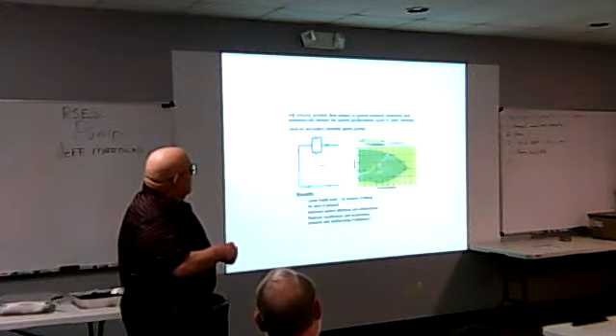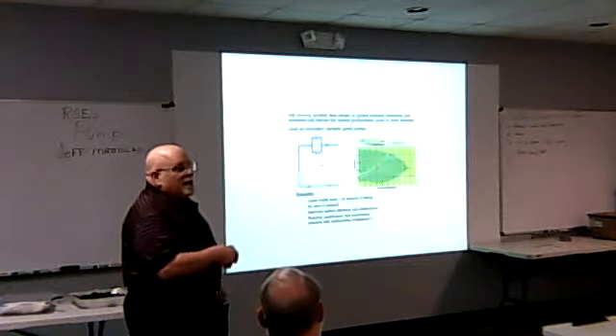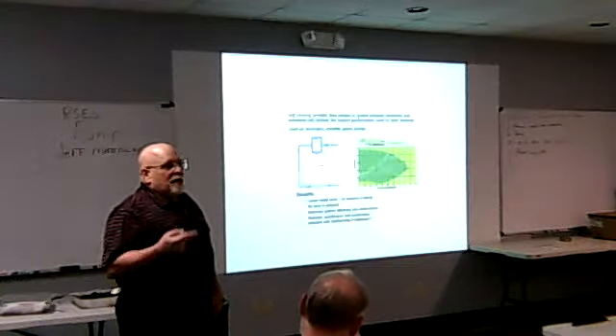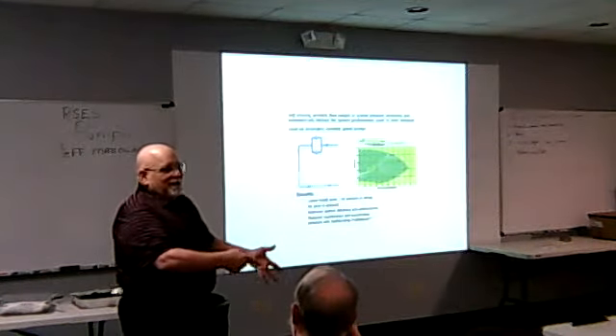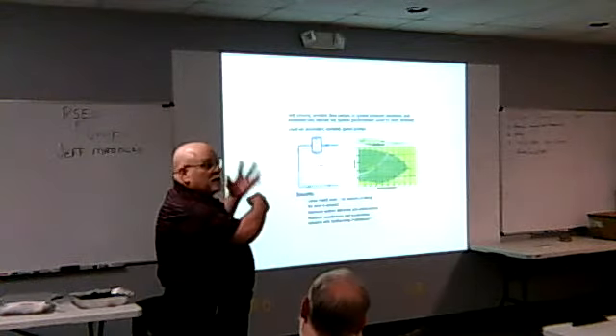Okay, so like I said, we have this system curve, but I know these impellers. I can say this impeller's here, this impeller's here, this impeller's here. Now I've got defined points where I know I have to be. And when we go in the field, we'll go in and actually take a head measurement. We'll guess at it, set it, then we'll go out in the field, take a real reading, and then change the programming, so it's running dead on that system curve.